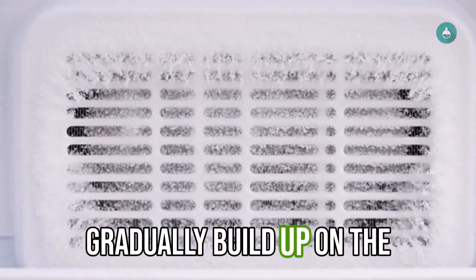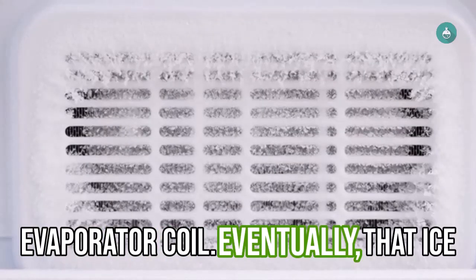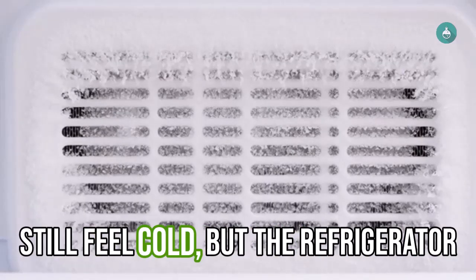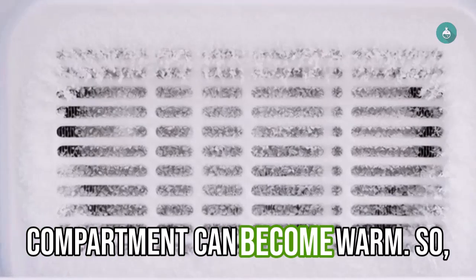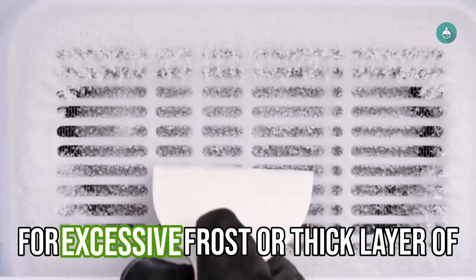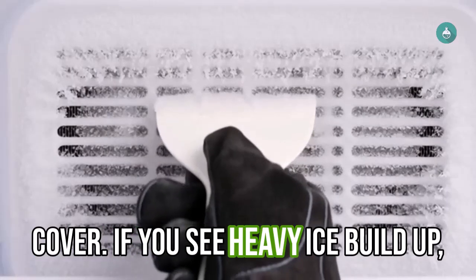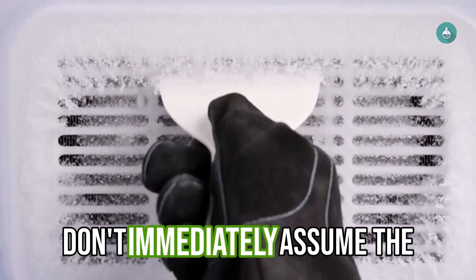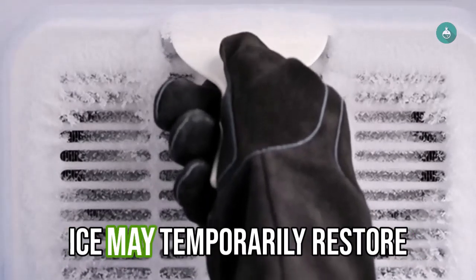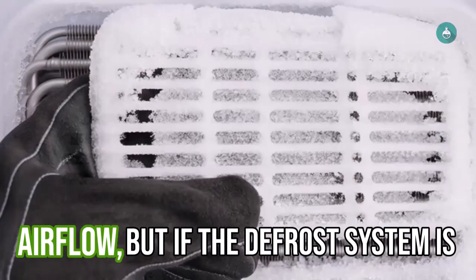If the defrost system fails, ice can gradually build up on the evaporator coil. Eventually, that ice can block airflow. The freezer may still feel cold, but the refrigerator compartment can become warm. So how can you recognize this problem? Open the freezer and look for excessive frost or a thick layer of ice around the rear evaporator cover. If you see heavy ice buildup, don't immediately assume the refrigerator simply needs to be defrosted.